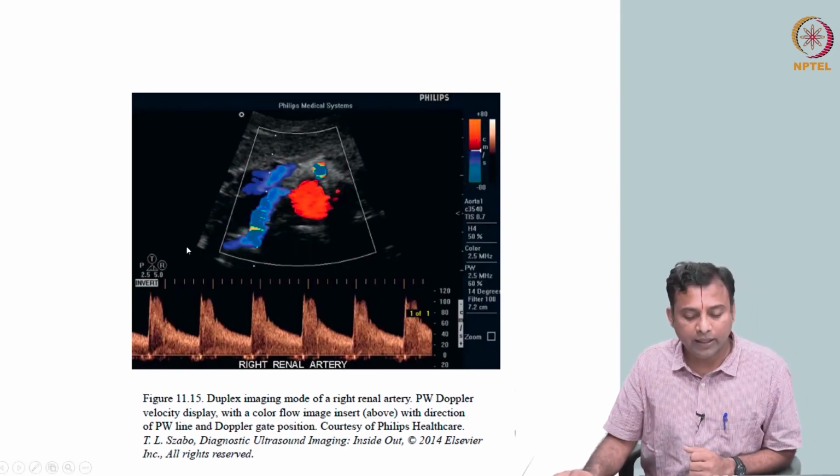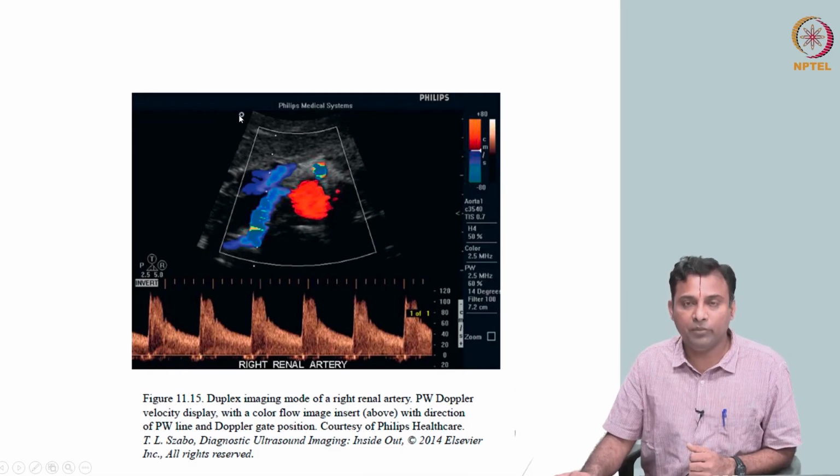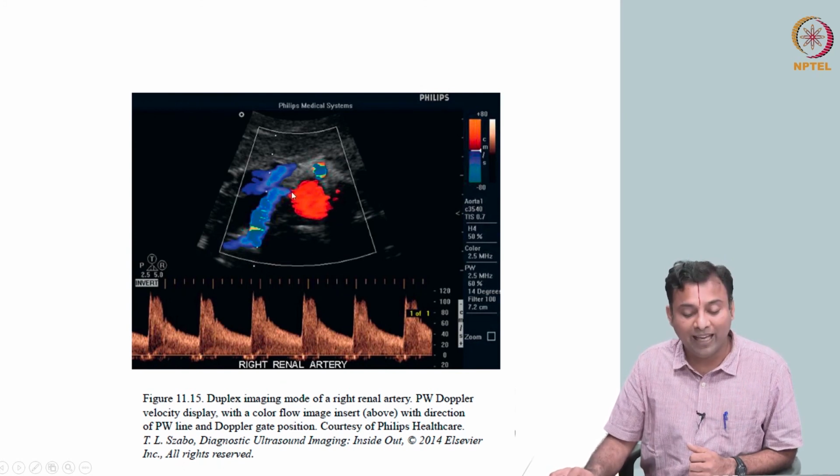So you know how this gray image is formed, right, your B mode image. After you see a B mode image, you know where some flow is going to be. So what you see here is a duplex image. Wherever there is velocity, the velocity using the Doppler principle is calculated, color coded, and overlaid on the B mode. You can see the color bar is in centimeters per second. Again, like I said, if it is flowing towards the transducer, it is one color, flowing away from the transducer is another color.